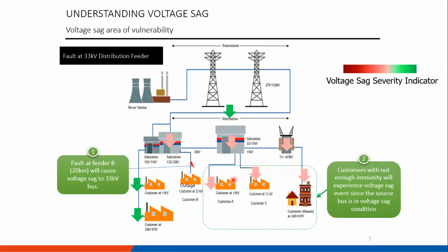Any substation or customers connected to this substation will also experience voltage sag, especially customers with not enough immunity. Then, another transformer for our low voltage customers, since it's connected to the same bus bar, will also be affected by voltage sag if they don't have enough immunity. So this is a 20 kilometer fault. However, the customer connected to the next feeder, with a different transformer and different bus bar, may have some effect, but it's still in the green zone, maybe around 80-90% voltage. And the transmission is not severely affected. Yes, there will be some drop, depending on the severity of the fault, but it's still in the green zone. So this is an example of a voltage sag that happens 20 kilometers from the substation.